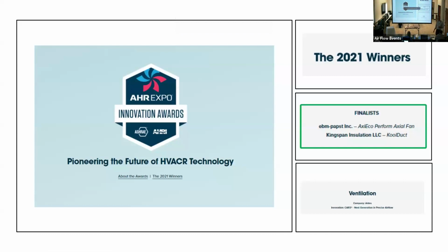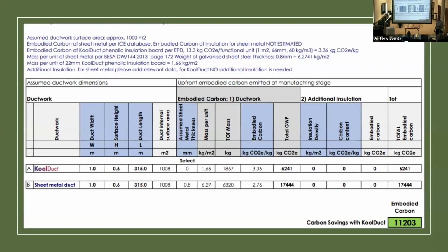Okay, incidentally, this Koolduct product won an innovation award a few years ago. And something else that's come up, when you use Koolduct instead of galvanized, this is the carbon footprint, the embodied carbon of the product. With galvanized it uses a lot of fossil fuels. And so this is just a comparison of about 1/3 the carbon footprint using Koolduct versus metal. And I'm sure there's lots of variations on this. This is a low pressure ductwork comparison, but someday we're gonna probably get to the point where we're measuring all the stuff that goes into the building and taking it into account instead of just what we're burning while we have the building. So we may see more phenolic ductwork coming up in the future.